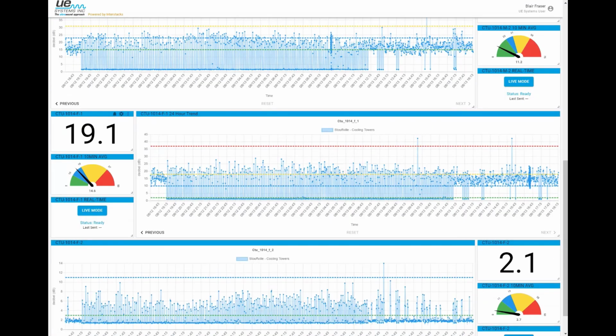If I scroll down to the fan inboard bearing, you will notice it is in the blue zone. This is a bearing that requires lubrication. In fact, the customer knows this and will go out and lubricate it. Right now, that inboard bearing is reading 19.1 with a baseline of 4 decibels, so we are 15 decibels over that baseline, which is concerning, meaning that bearing requires lubrication before some damage is set to that. So what that customer would then go do is use the OnTrak to lubricate that device.